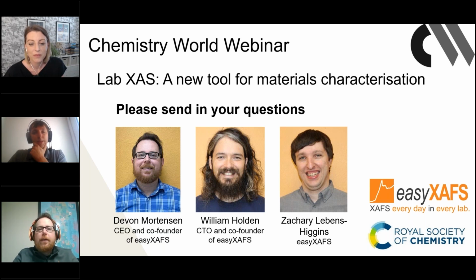Yes, absolutely. Like I said, powders are pretty common. For powders, first you determine how much of the material you need, and we have tools built into the software that help you do that, usually on the scale of a few milligrams. You want to make sure you have a uniform sample, so you don't want isolated particles, so you grind it up. We'll usually add a binder material to help it hold together, and that gets put into a die cast and pressed into a pellet. So that's for powders.